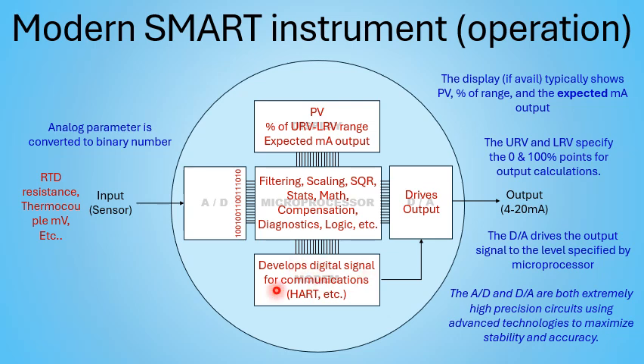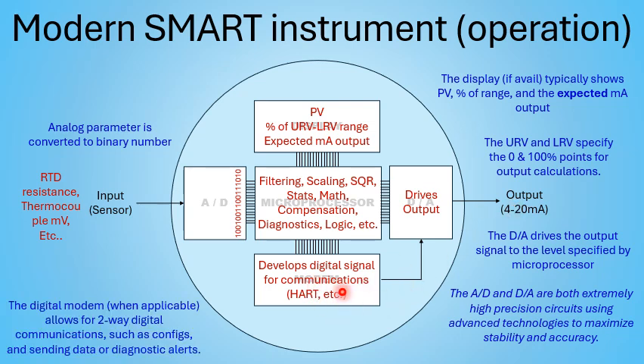So the modem actually develops a digital signal for communications. Typically, on a lot of our instruments, that's going to be that HART signal that rides on top of the 4 to 20 milliamps. But it could also be Foundation Fieldbus that just goes direct. That modem allows for two-way communication. So not only can it send out information, additional data, in addition to the PV that you're sending out over your signal, but it can send secondary and tertiary variables, things that are really helpful sometimes. So pretty powerful little instrument. And individual instruments have way more features and functionality, but this is kind of the typical.